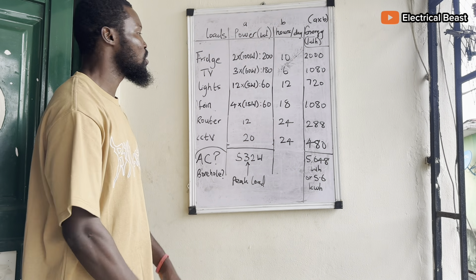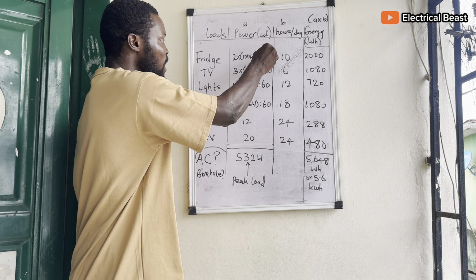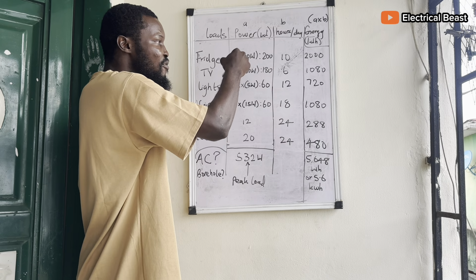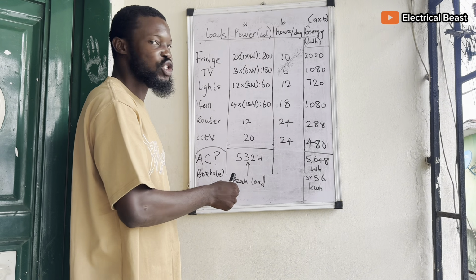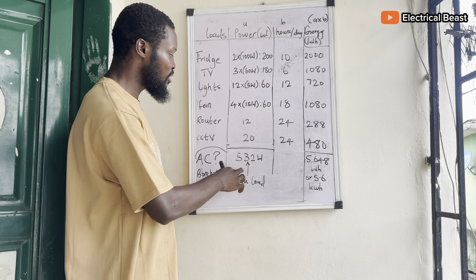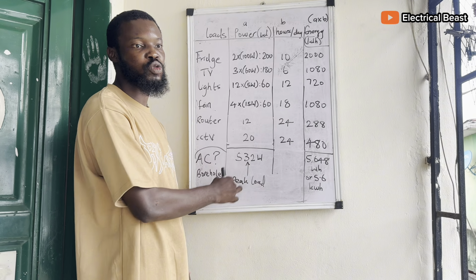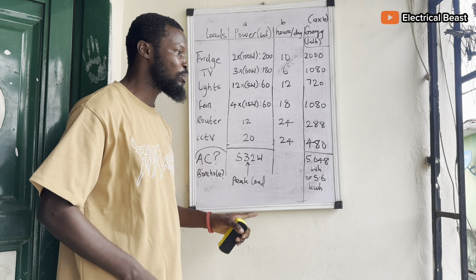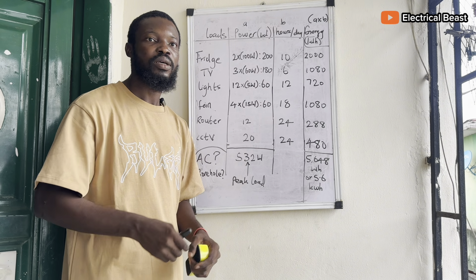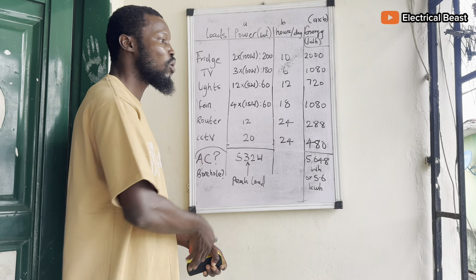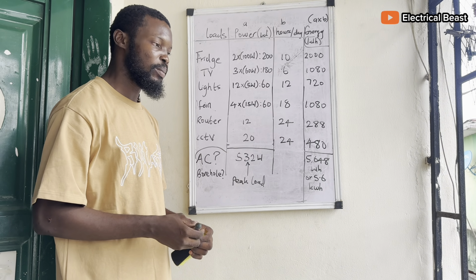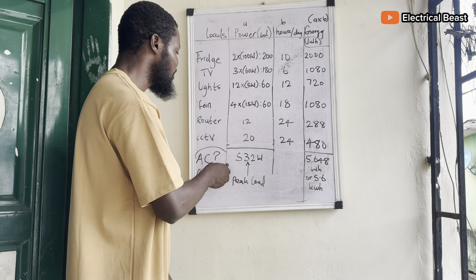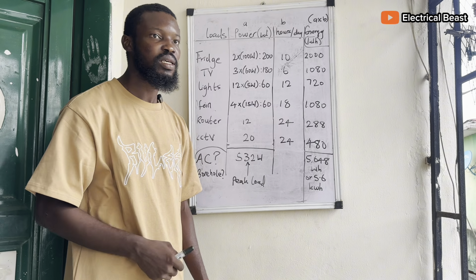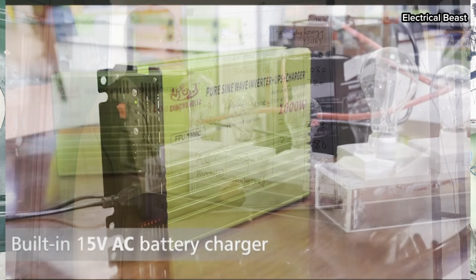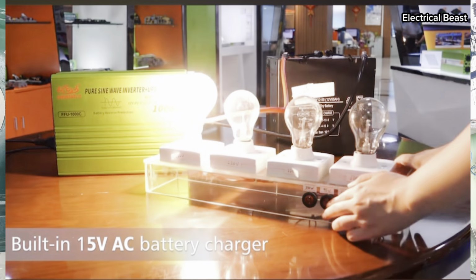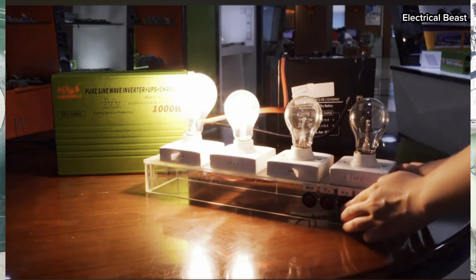Now the peak load is the sum total of the individual wattage of every load that you have here. So when you sum everything together, you have 532 watts in total. So this is your peak load. With the peak load, you have an idea of the size of inverter that can power all these things. Now, mind you, the fact that you have 532 watts here doesn't mean that you need just a little above 532 for the size of your inverter to be able to power your load.